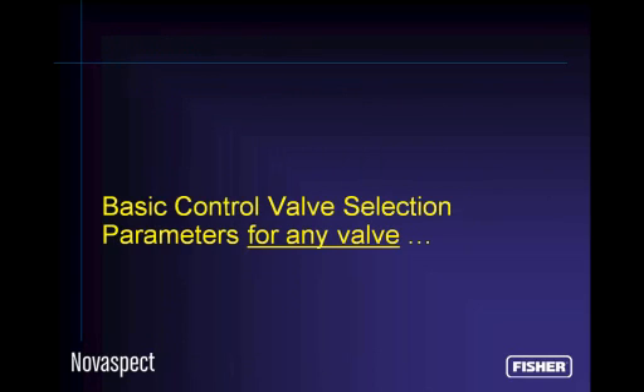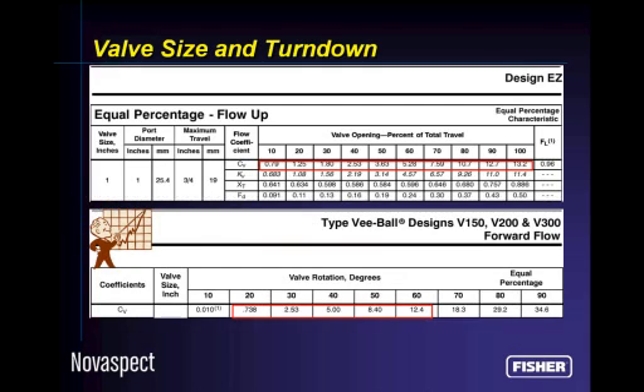Let's talk about the basic control valve selection parameters for any valve. This would be any valve that's in your universe of control valves in your plant. We need to employ certain engineering practices to make sure that we pick the right valve. First of all, of course, we're concerned with the size and the turn-down capability of your valve. So we go through a process which we call the sizing process. Maybe many of you out there even have Fisher or other software on your computers, and you try to accomplish this task on your own. In essence, we're inputting a bunch of process data and thermodynamic characteristics about the fluid that flows through the valve, and we're calculating a sizing coefficient, and from there we look at our charts and pick a valve size that's appropriate to the application. And hopefully the same valve works well at the max flow condition and the min flow condition.